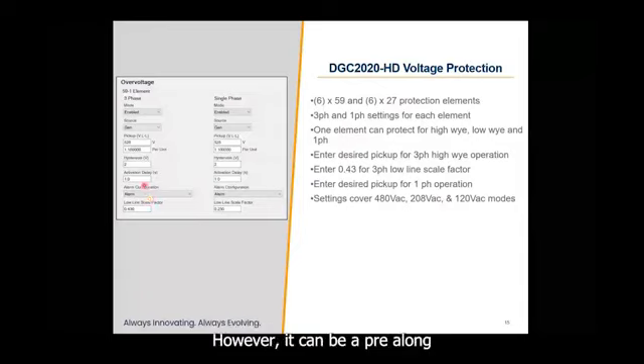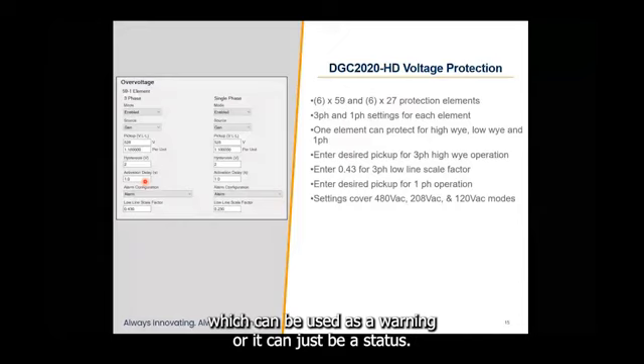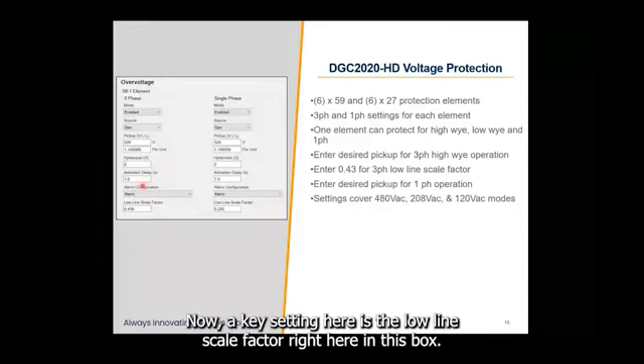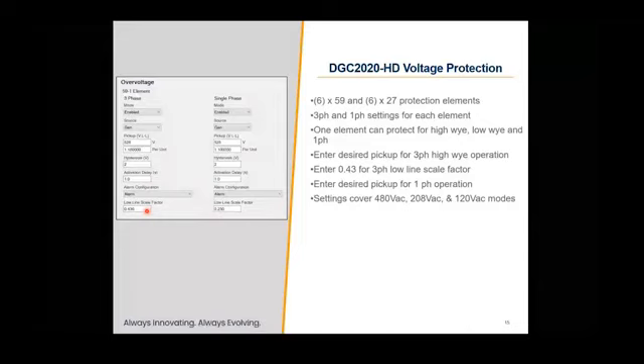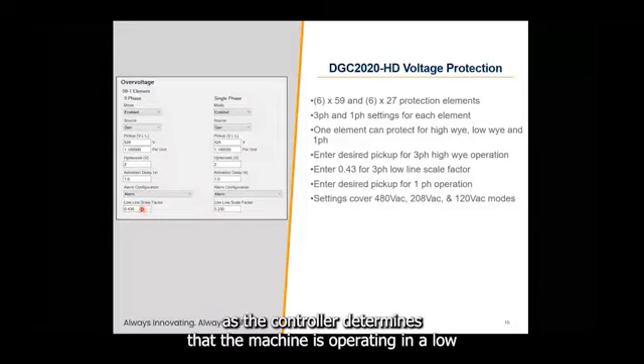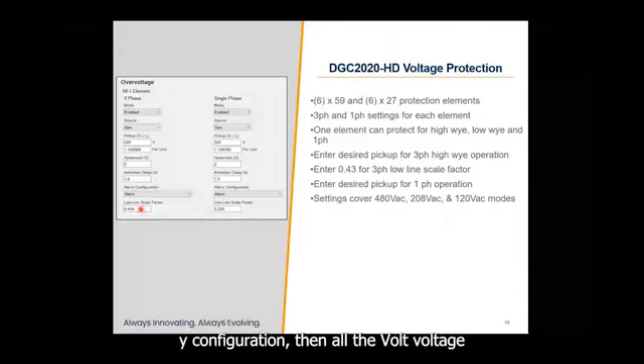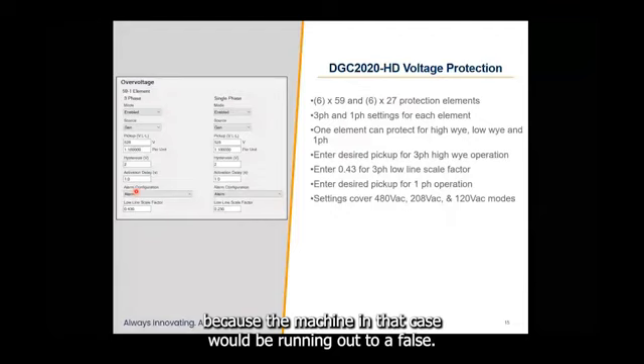However, it can be a pre-alarm, which can be used as a warning, or it can just be a status. Now, a key setting here is the low line scale factor. Right here in this box, I have 0.43. As soon as the controller determines that the machine is operating in a low Y configuration, then all the voltage protection settings get multiplied by 0.43, because the machine in that case would be running at 208 volts.